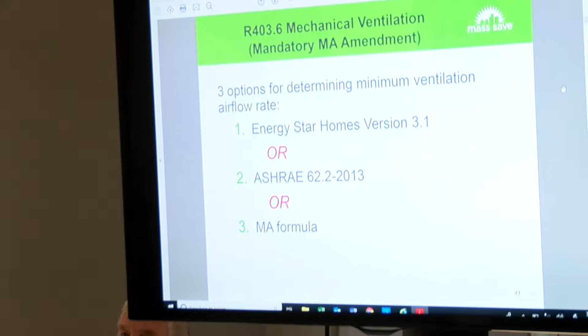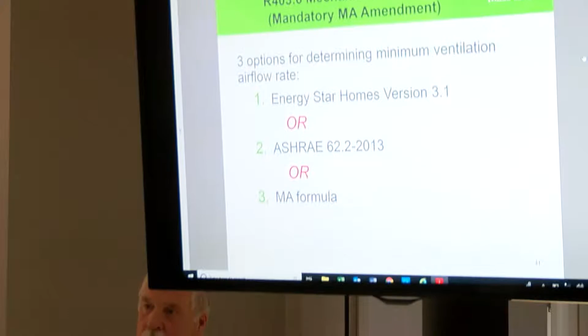So there's 3 main compliance methods that we use: Energy Star, ASHRAE, or the Mass formula. Each one of those formulas basically takes into account your designed air changes an hour of the home, then at the end, your final test, your actual air leakage per home. That calculates into a lengthy formula that's based on how many bedrooms, how many square feet, how much glass area you have in the home, and that gives us the ventilation requirement that is recommended by whichever one of these formulas. So you do all those calculations at the end, and then you tell them how long the fan's going to be ventilating for. And then we set it. We actually set it while we're on site, and we certify it before we leave.